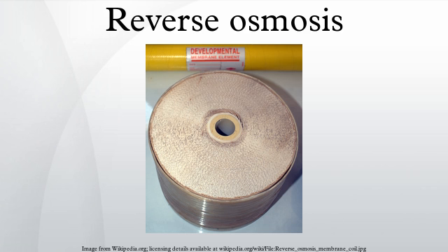Desalination. Areas that have either no or limited surface water or groundwater may choose to desalinate. Reverse osmosis is an increasingly common method of desalination, because of its relatively low energy consumption. In recent years, energy consumption has dropped to around 3 kWh per meter 3, with the development of more efficient energy recovery devices and improved membrane materials.